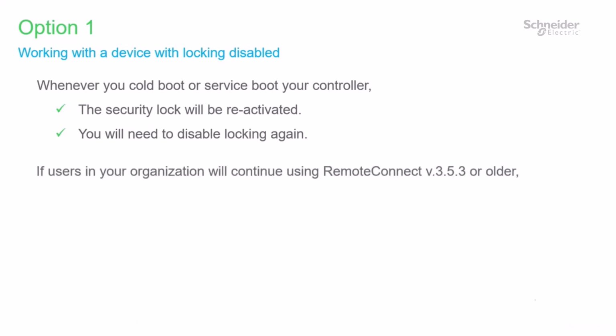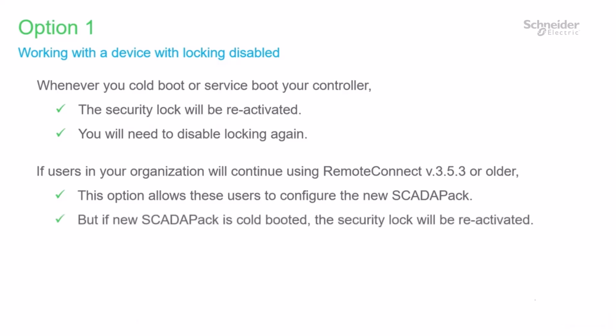If you have users in your organization that intend to remain using RemoteConnect 3.5.3 or older, disabling the security lock will allow these users to configure the RTU without issue. However, if one of these users needs to cold boot the controller, the security lock will be reactivated, and only RemoteConnect 3.6.3 or newer can disable locking at that point. All the more reason to have all users update their PCs with the latest version.